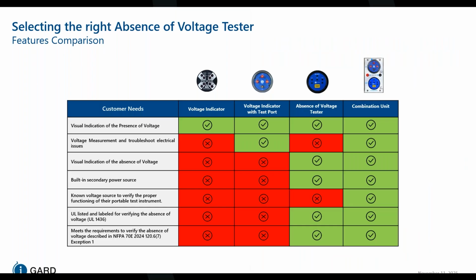Now, here's the comparison of the units between the individual absence of voltage tester, the individual voltage indicator with test ports, and the simple voltage indicator, and the combination unit, which indicates that the combined i-AVT Plus will have all the features of voltage indication, test ports, and absence of voltage in one enclosure.